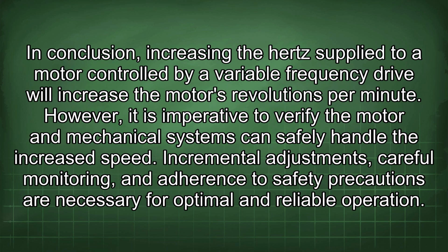In conclusion, increasing the Hertz supply to a motor controlled by a variable frequency drive will increase the motor's revolutions per minute. However, it is imperative to verify the motor and mechanical systems can safely handle the increased speed. Incremental adjustments, careful monitoring, and adherence to safety precautions are necessary for optimal and reliable operation.